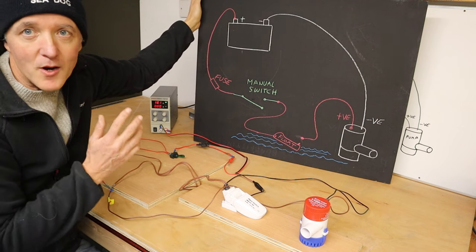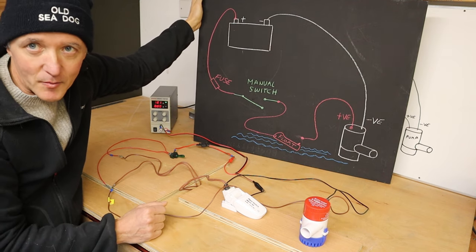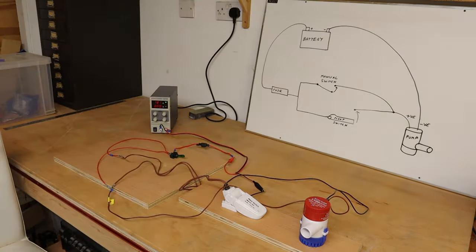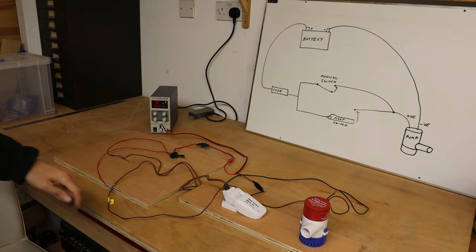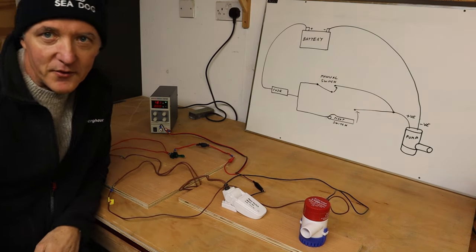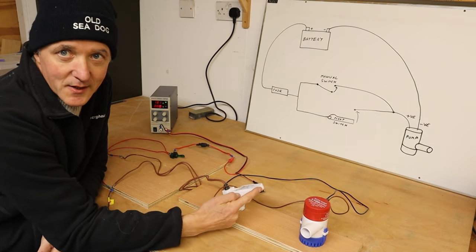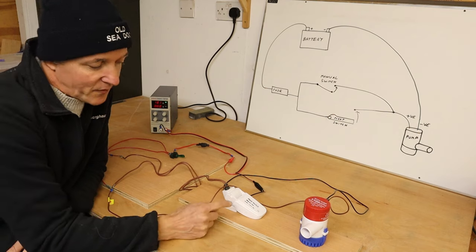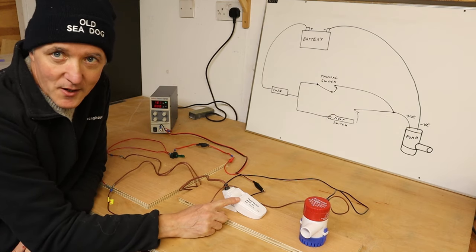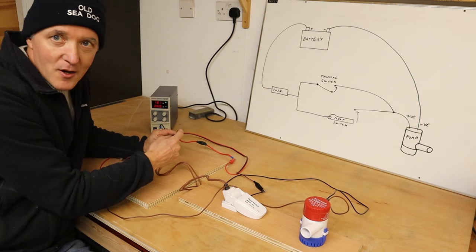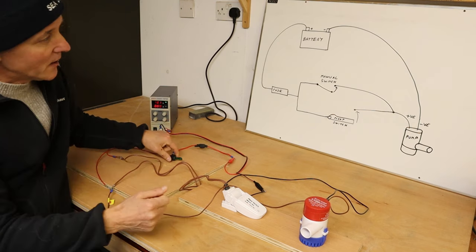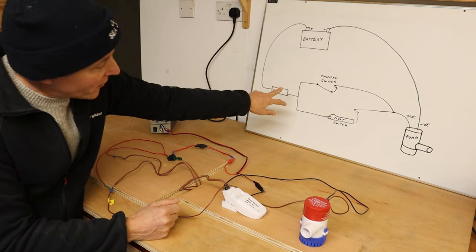So that brings us to a way of wiring things a little bit differently that improves on that situation, which is what we've done today. In this system, the system can be operated by the float, but if for any reason the float didn't work or didn't function, we've got a manual override switch. So that is shown on this circuit diagram here.